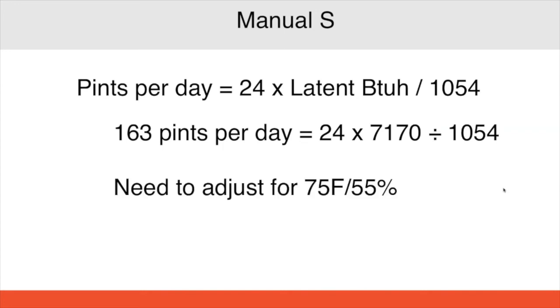And then also Manual S says, okay, but now we need to adjust a dehumidifier's pints per day for 75 degrees and 55% RH, because all dehumidifiers are rated at 80 degrees and 60% relative humidity traditionally in the past. Now, the DOE has come up with new testing conditions for whole house versus crawl space and basement, but right now Manual S says we need to adjust the pints for that 75 degrees and 55% relative humidity. So if you were to take our 205 pint unit and do the 0.76 multiplier to get for that 75 and 55, it's going to tell you that that 205 pint dehumidifier is really about 156 pints.